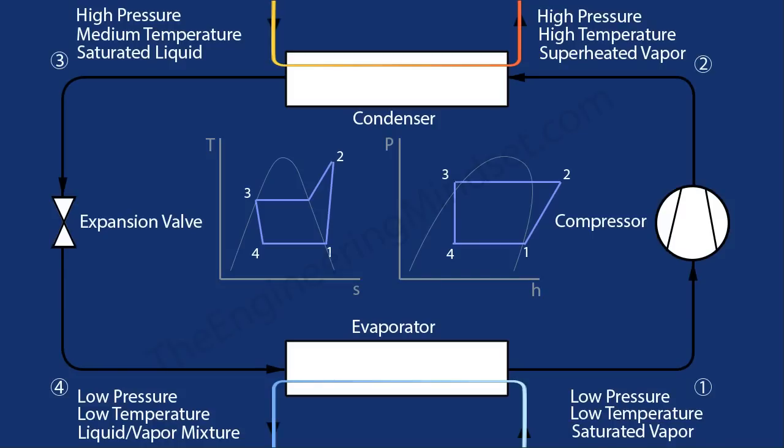As with all the expansion valves featured in this video, you can see the performance on this chart. The expansion valve is located here, going from point 3 to point 4, meaning the refrigerant changes from high pressure to low pressure, from medium temperature to lower temperature, and from a saturated liquid to a liquid-vapor mix. On the pressure axis you can see a decrease in pressure, a decrease in temperature, an increase in entropy, and a consistent enthalpy.